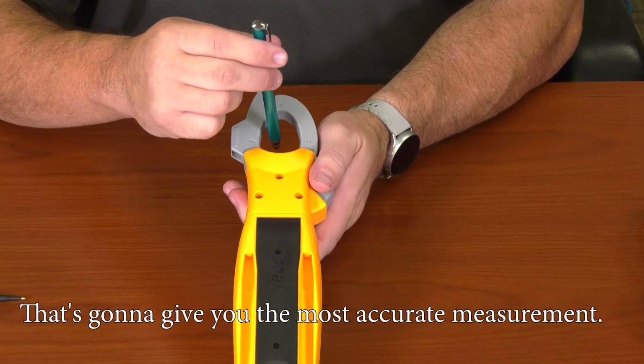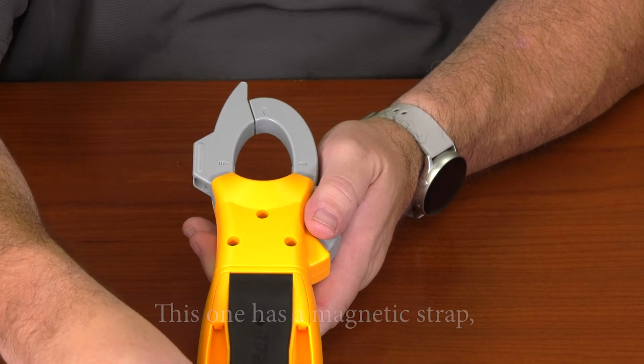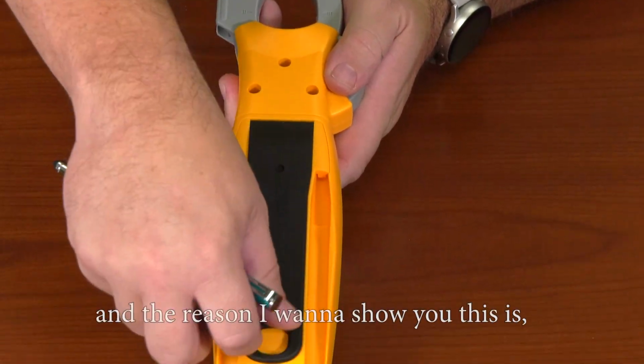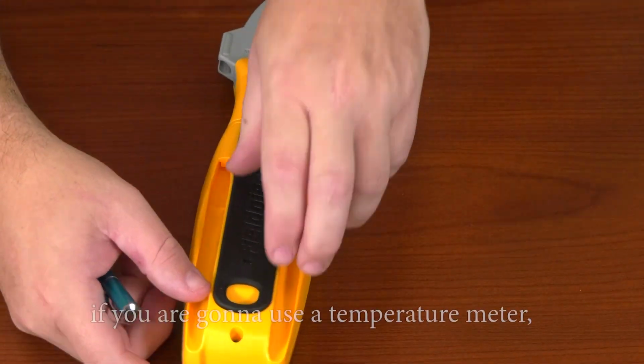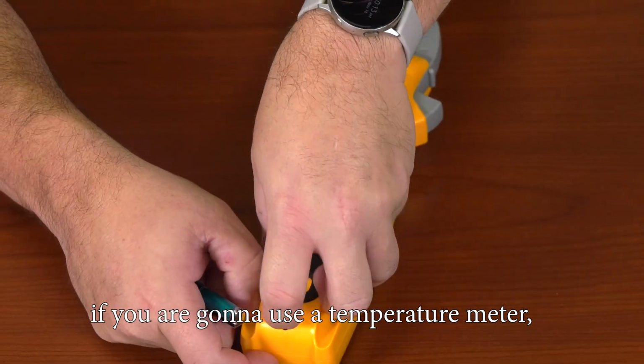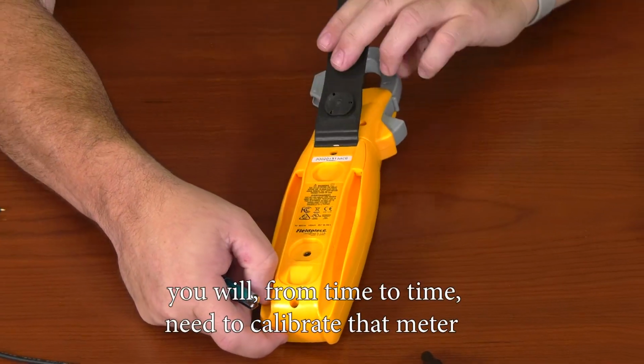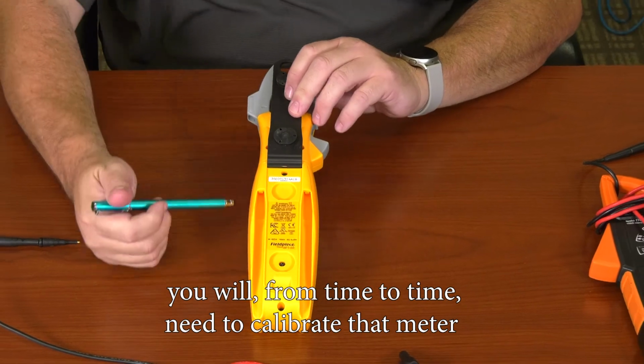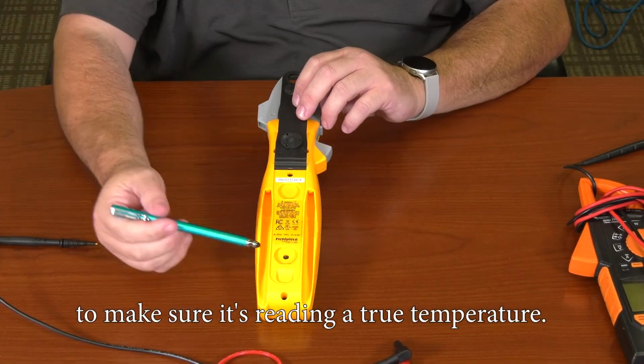That's going to give you the most accurate measurement. Okay. This one has a magnetic strap, and the reason I want to show you this is if you are going to use a temperature meter, you will from time to time need to calibrate that meter to make sure it's reading a true temperature.